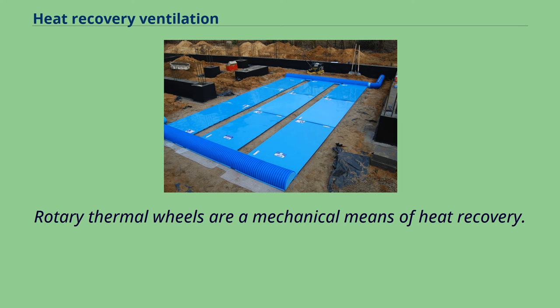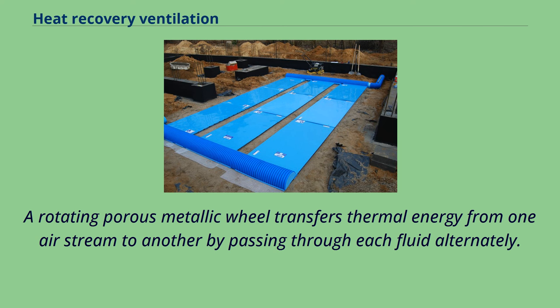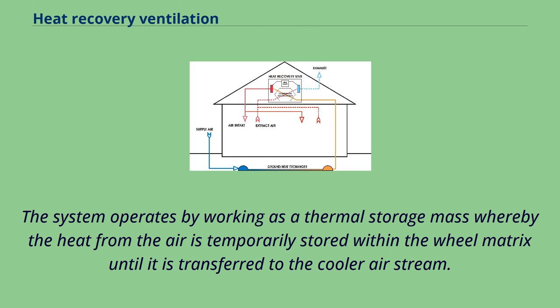Rotary thermal wheels are a mechanical means of heat recovery. A rotating porous metallic wheel transfers thermal energy from one air stream to another by passing through each fluid alternately. The system operates as a thermal storage mass whereby the heat from the air is temporarily stored within the wheel matrix until it is transferred to the cooler air stream.